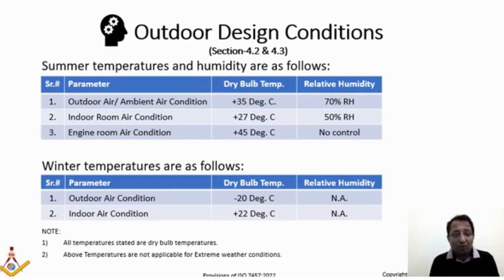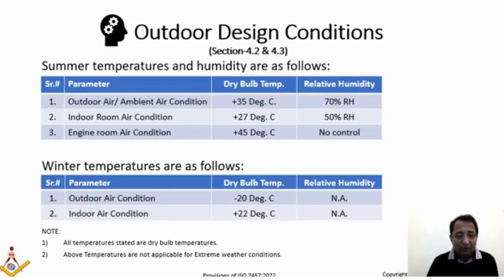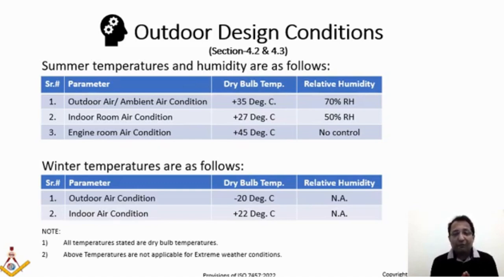For winter temperatures, the outdoor air condition is minus 20°C and the indoor condition is plus 20°C to maintain. All temperatures selected are dry bulb temperatures. There is no wet bulb specified, since for summer conditions 70% RH is already stated, and for winter there is no relevance of relative humidity. These temperatures are not applicable for extreme weather conditions. Heaters are therefore needed to achieve plus 20°C indoors from minus 20°C ambient.